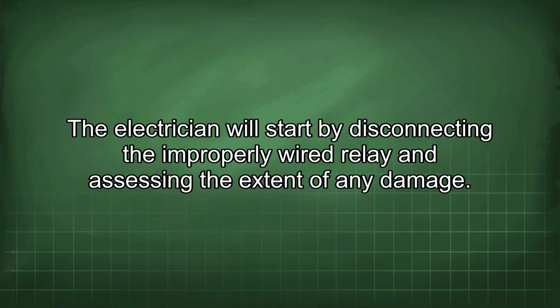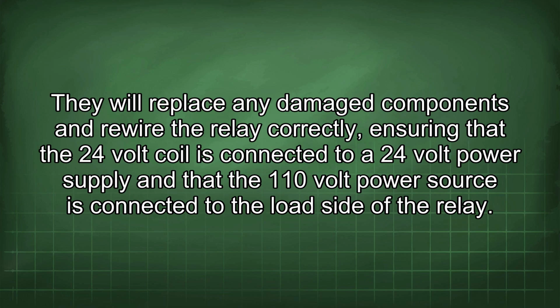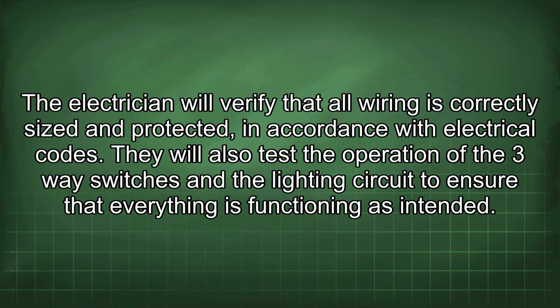The electrician will start by disconnecting the improperly wired relay and assessing the extent of any damage. They will replace any damaged components and rewire the relay correctly, ensuring that the 24-volt coil is connected to a 24-volt power supply and that the 110-volt power source is connected to the load side of the relay. The electrician will verify that all wiring is correctly sized and protected, in accordance with electrical codes. They will also test the operation of the three-way switches and the lighting circuit to ensure that everything is functioning as intended.